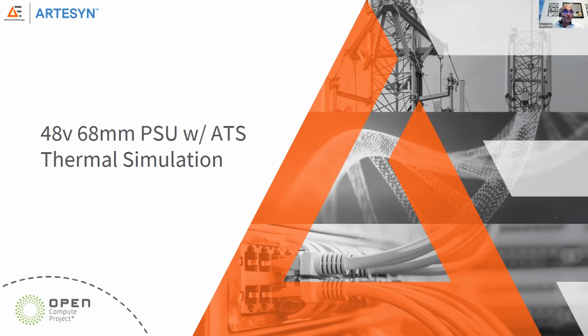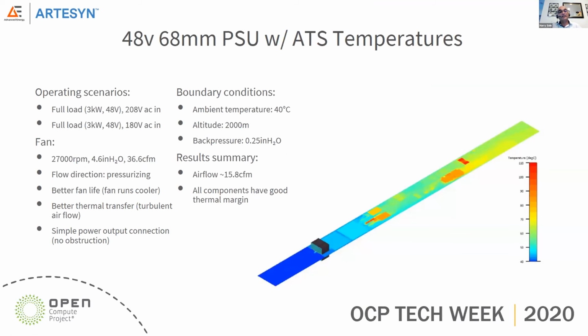The next slide shows the general guidelines for the thermal simulation we did. The thermal simulation has been done in two key scenarios, both at full load: 208 volts nominal operation, as well as 180 volts, which is one of the stringent conditions. We also keep in mind the ambient condition is 40 degrees C, 2000 meter altitude, with the required back pressure. As you see from the FloTHERM simulation, the power supply has got a very good thermal margin at the right airflow, and it's well within the guidelines.